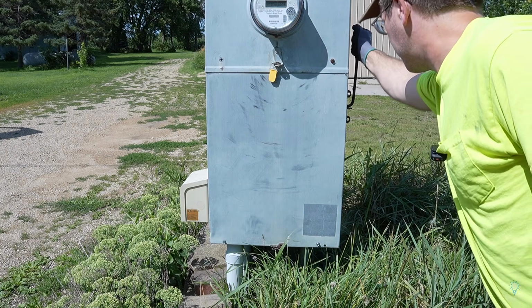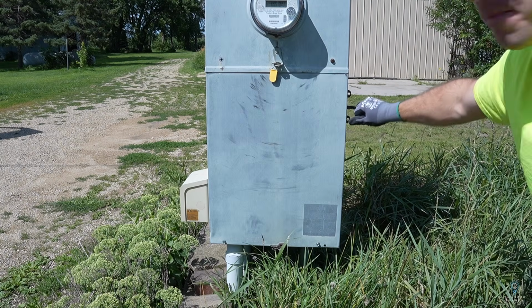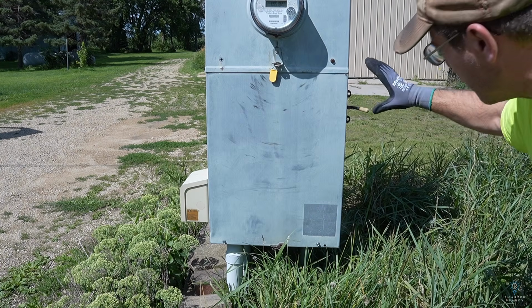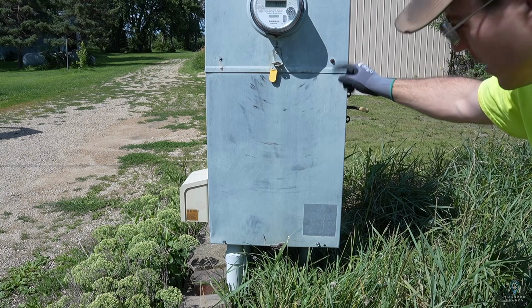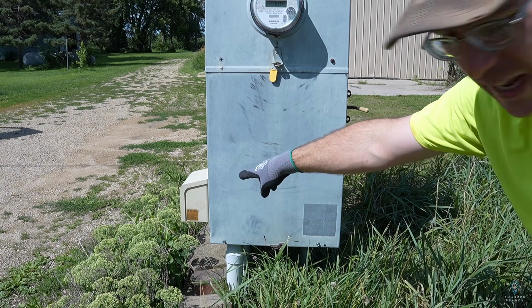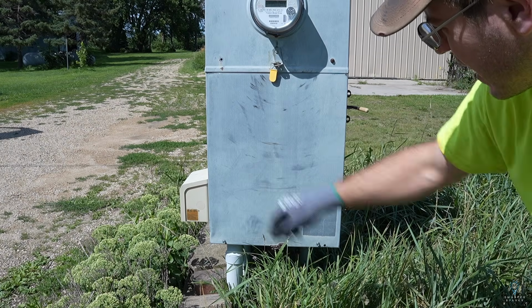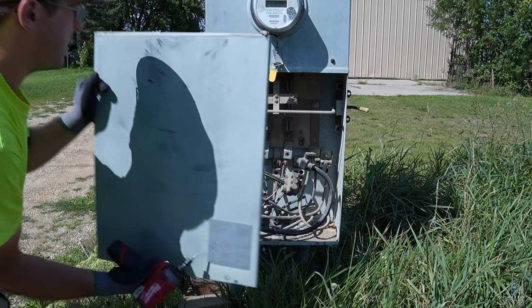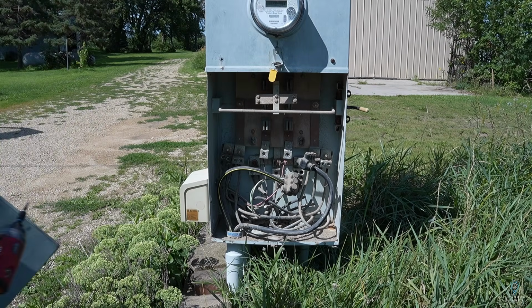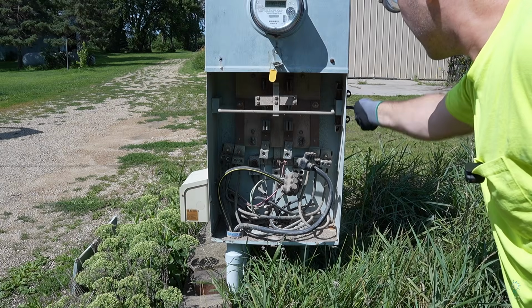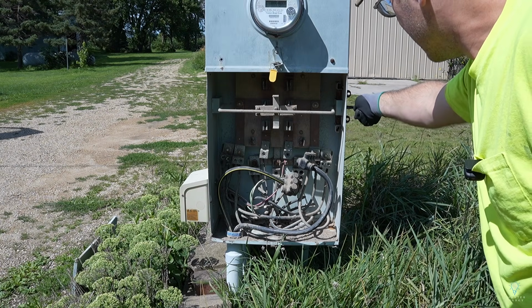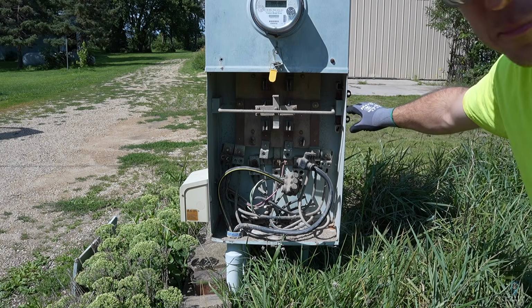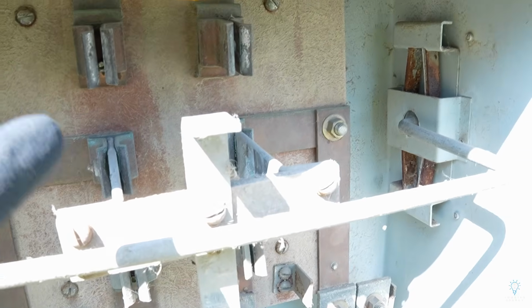So we're gonna go ahead and pull this to the middle. And because this is a transfer switch, the middle is off. Up is utility power and down is generator power. And that's what that device is over there. That is a generator inlet. I can physically see that the incoming power is disconnected. There, so now the switch is physically in the middle. Those lugs right up top there, those are still live, coming right from the meter socket. So gonna have to avoid those, but everything from here down is now completely dead.